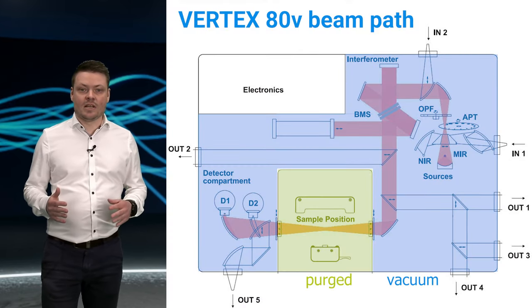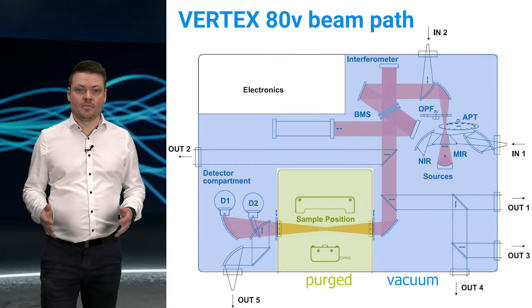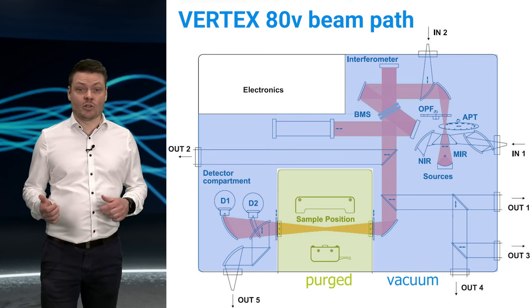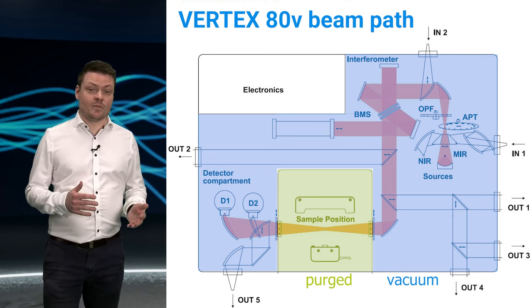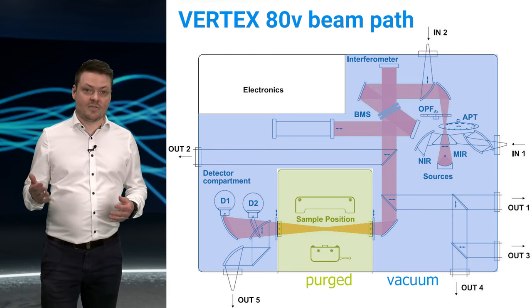Vacuum systems even offer advantages for samples that can't be brought into the vacuum. An example for that would be protein studies in life science. These samples are typically in aqueous solution and therefore can't be brought into the vacuum. However, in Vertex systems it is possible to just evacuate the optical compartment. This way you still have most of the beam path under vacuum conditions. Protein bands overlap with water bands, so the reduction of the water influence is crucial here to detect small signals and to detect subtle changes over time.